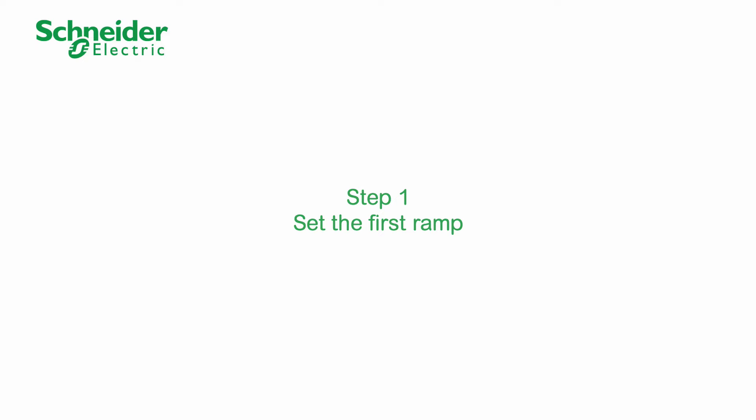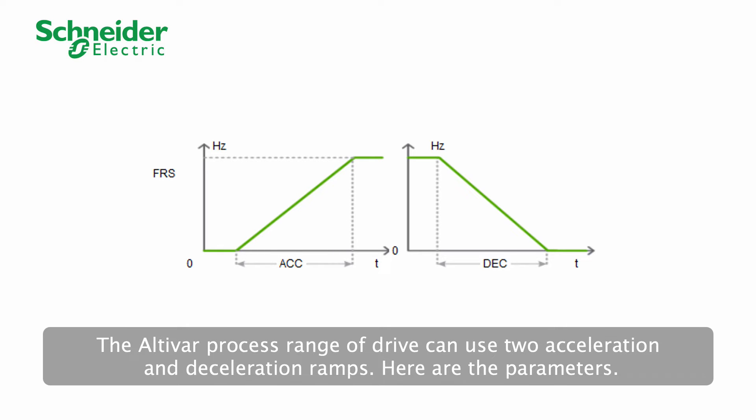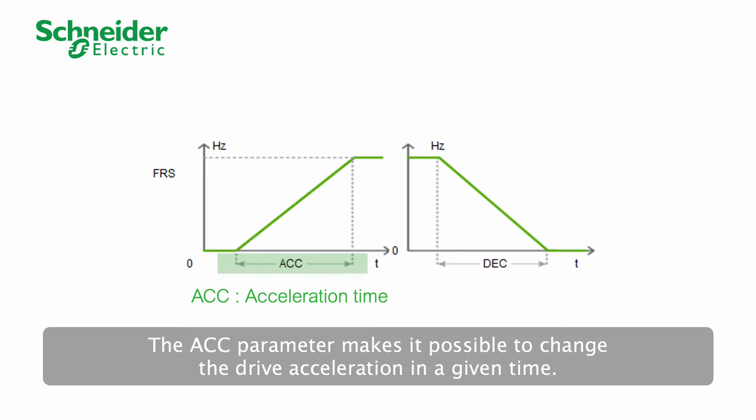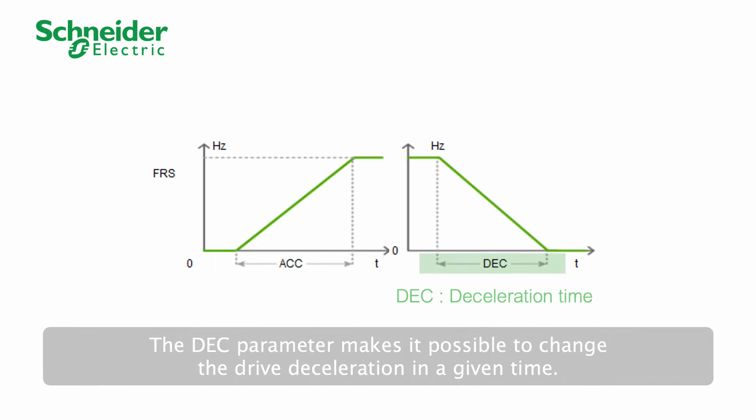Set the first ramp. The Altivar Process range of drive can use two acceleration and deceleration ramps. Here are the parameters. The ACC parameter makes it possible to change the drive acceleration in a given time. The DEC parameter makes it possible to change the drive deceleration in a given time.